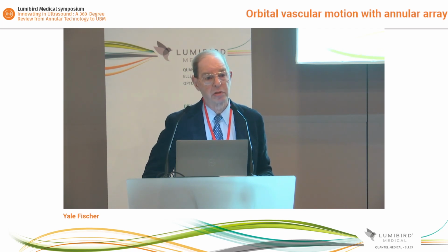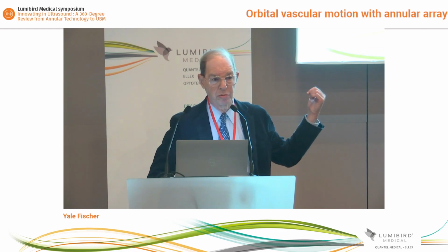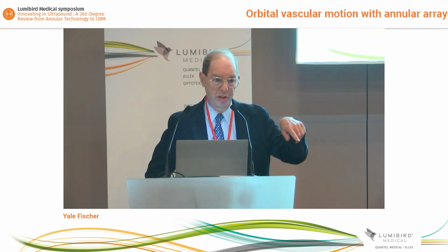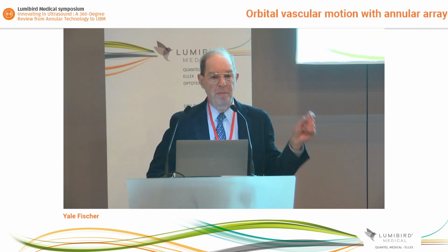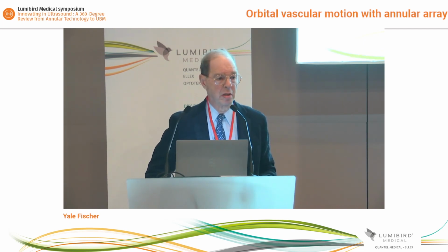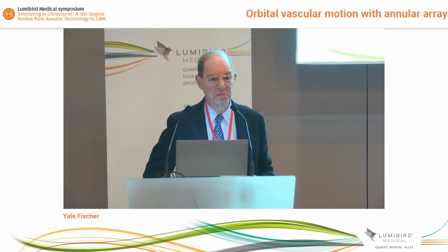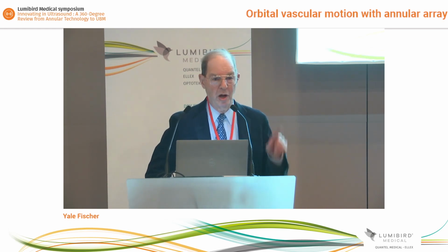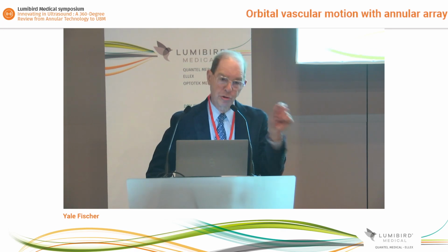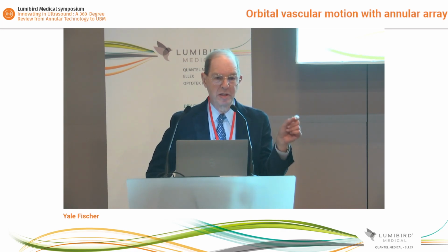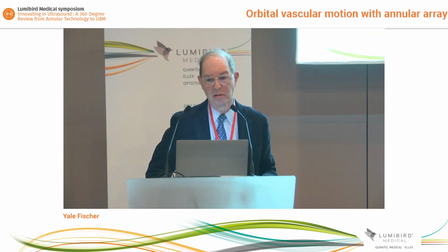There's a reason they don't tell you. And the reason is simple. It's the same reason that we get for the ultrasound, because that's how they figured out how to do OCT. It's by the shape of the beam. The width of the beam determines your lateral resolution. So, what's the lateral resolution of a Heidelberg? About 25 microns, maybe if you're lucky. That's why you don't see cells. You don't see the rods separated from the cones, because they're smaller. And the beam is narrow, but not that narrow.